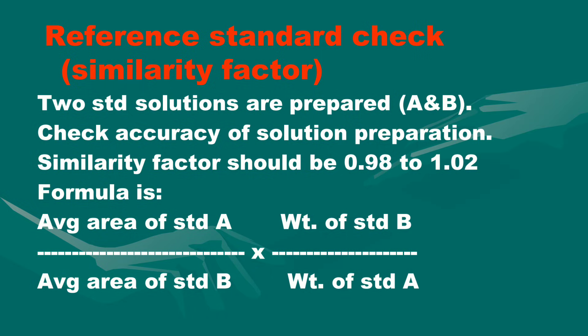Next is reference standard check, also known as similarity factor. In HPLC analysis, for the similarity factor, two standard solutions are prepared — standard A and standard B — to check the accuracy of solution preparation. The similarity factor should be 0.98 to 1.02. The formula to calculate the similarity factor is: (average area of standard A / average area of standard B) × (weight of standard B / weight of standard A).